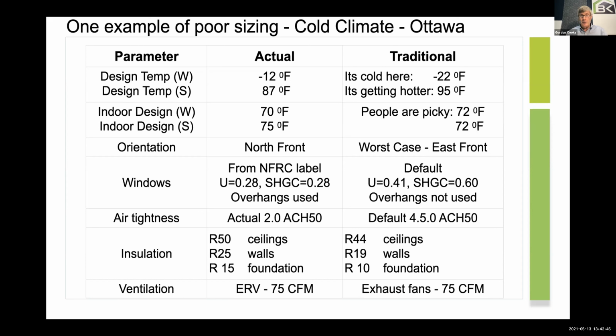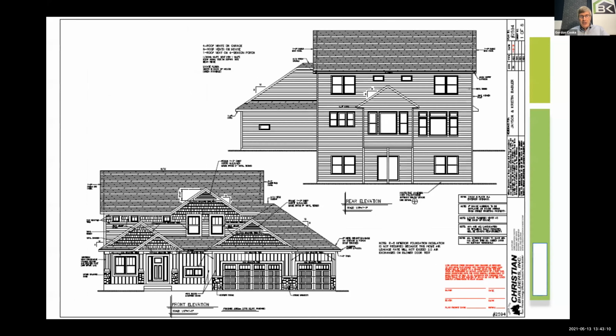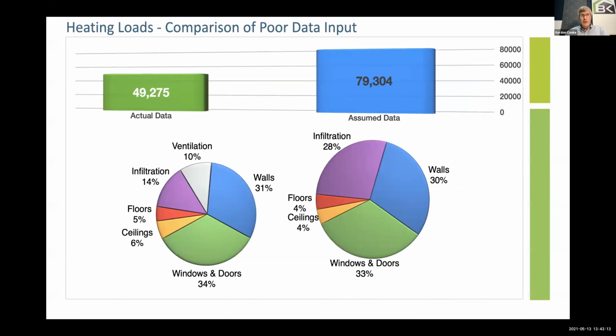But if you put it in at 72 and 72, and so on down the line, if you assumed worst case, east facing versus the actual, which was north facing, if you didn't use the right solar heat gain numbers, for example, you just use the default numbers that were in the software. If you didn't do the right air change, I just want to show you the difference that you would get. You're going to say, well, each one of those are small incremental changes. Right, they are. But look at the difference. There's the house that we were doing it on, by the way. And there's the difference between the assumed data, says 80,000 BTUs, 79,000, and the actual says 49,000 BTUs.